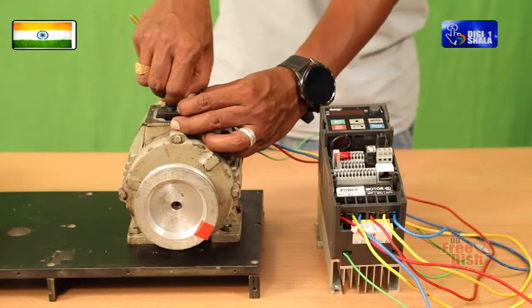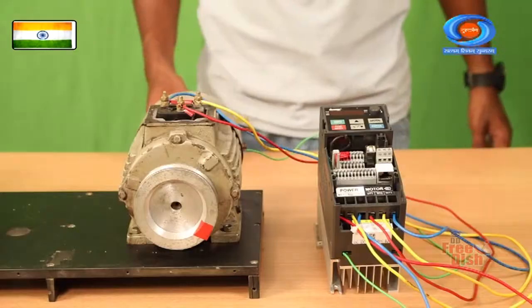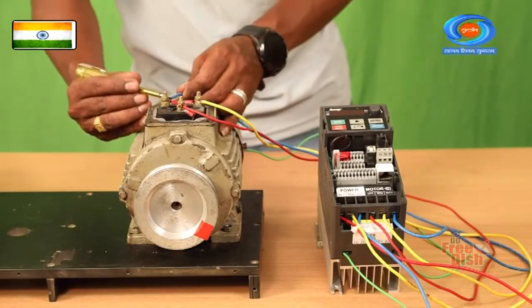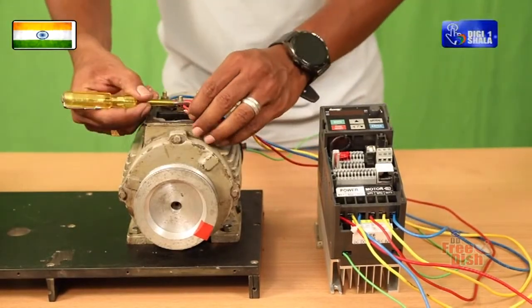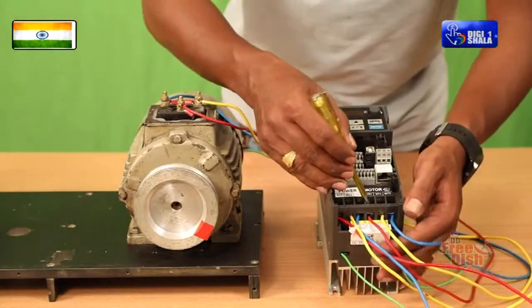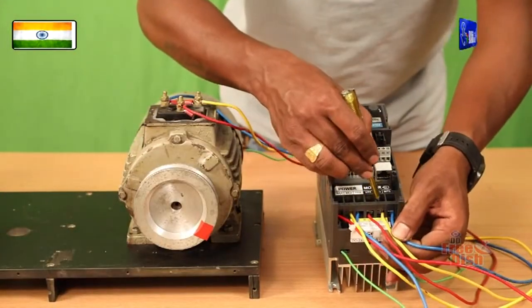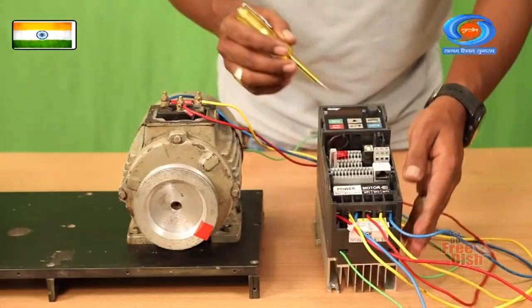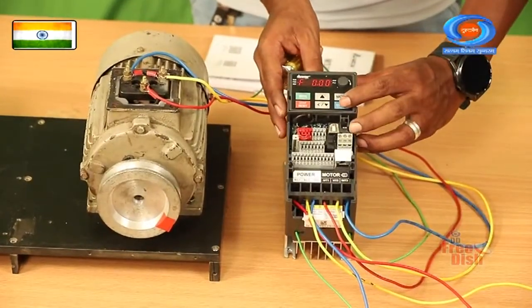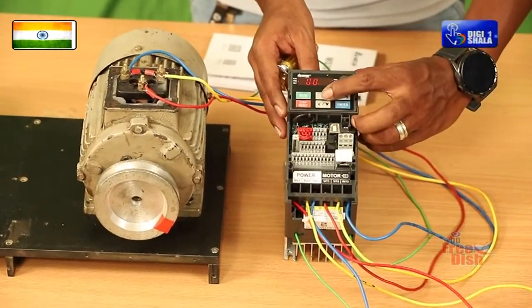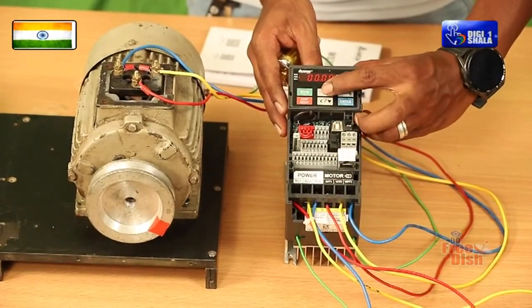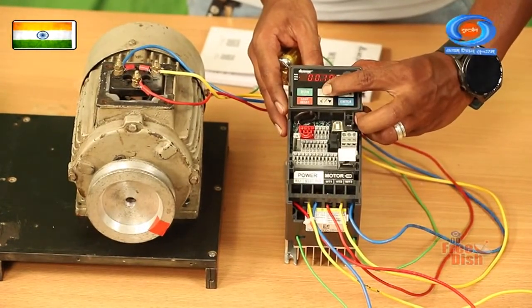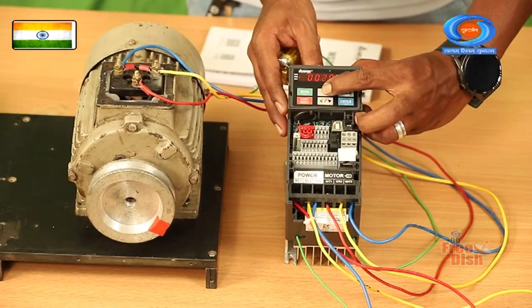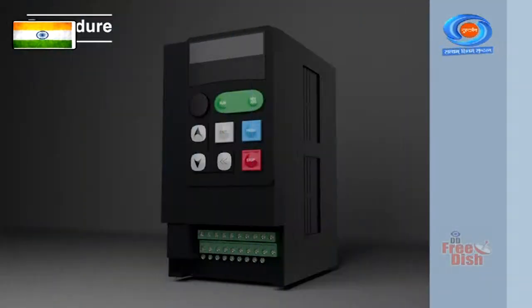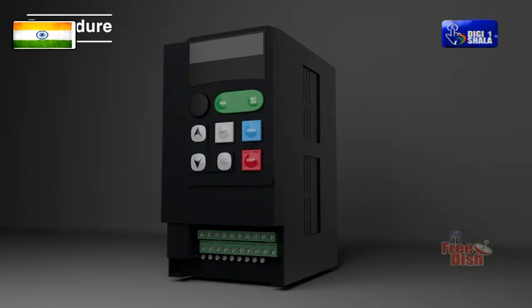Check connections. Once all connections are made, double-check all the wiring to ensure proper connections and no loose connections. Make sure all connections are secure and properly insulated. Power up. After verifying the connections, turn on the power supply and power up the AC drive. Check for any error codes or fault indicators on the drive. Our next task is to connect, run the motor and set the parameter for different speed.